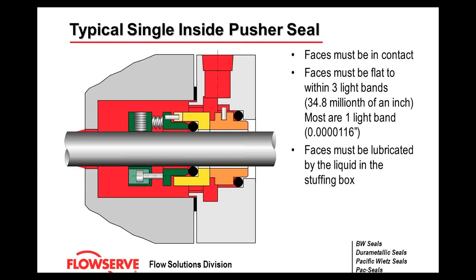What exactly does flatness mean? Picture yourself standing on a large concrete floor with a laser level. Someone in the distance takes measurements and you notice differences in elevation of one, two, three, or four inches — those are the valleys and peaks on that floor. If you were to shrink yourself down and do the same on a mechanical seal face, those differences in elevation could be no more than 34.8 millionths of an inch. That is what's meant by flatness.